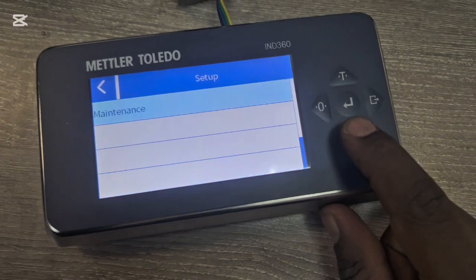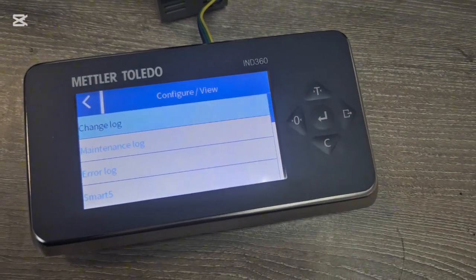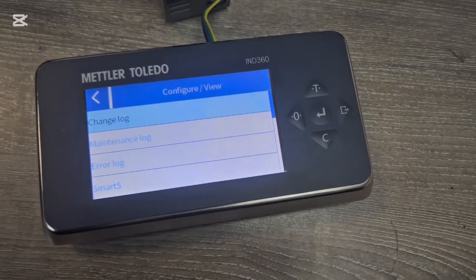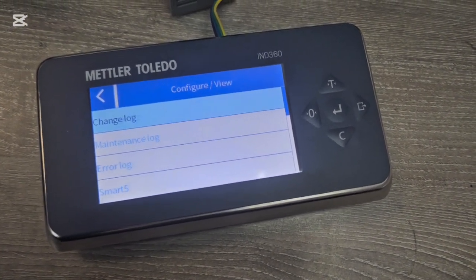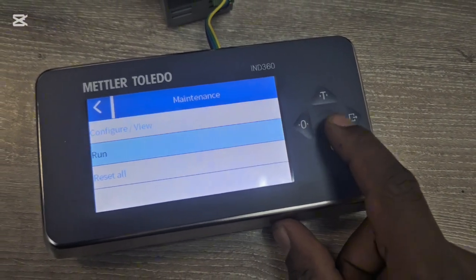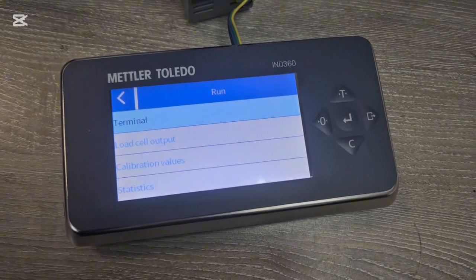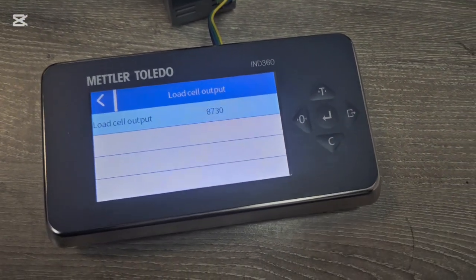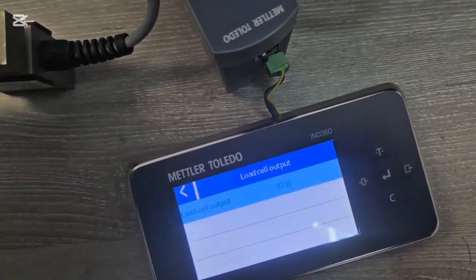Under Maintenance there's an important feature — under Configure View you can see error codes and the last faults that happened on the scale. If someone reported the scale was misbehaving during a night shift, you can check the maintenance log. You can also look at the live load cell output value, displayed as a count rather than millivolts. Currently it shows around 8,730.